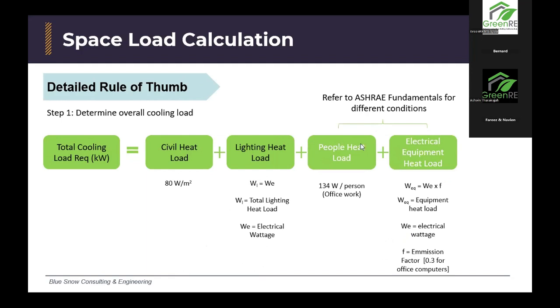By the way, if you're going to be getting involved in HVAC, get used to the concept of units changing from one to another, because some standards are written in imperial units, some standards are written in standard SI units. So it's a jumble. You need to be comfortable moving from one to another. So this, for example, is using 80 watts per square meter for just the civil load. Lighting load is the number of lighting fixtures you have in your space. We often take it as one-to-one. So for example, if your light has a 10 watts electricity rating, its heat load will also equate to 10 watts of heat.